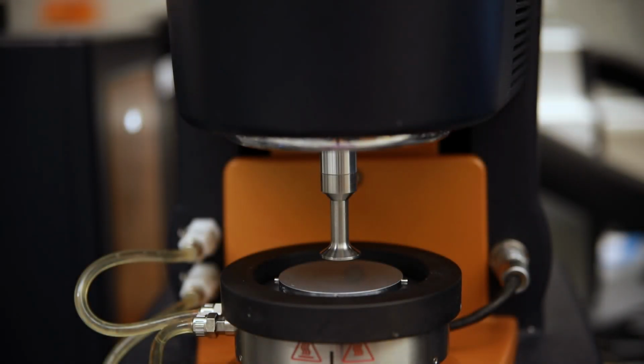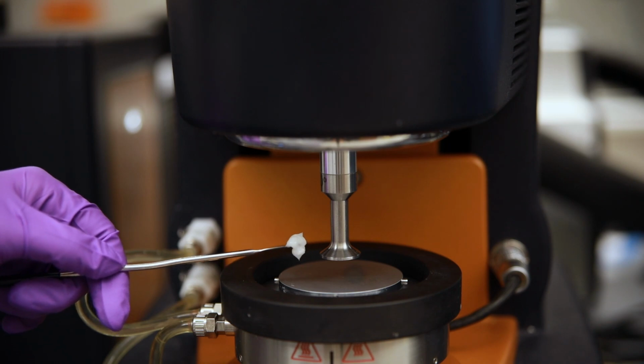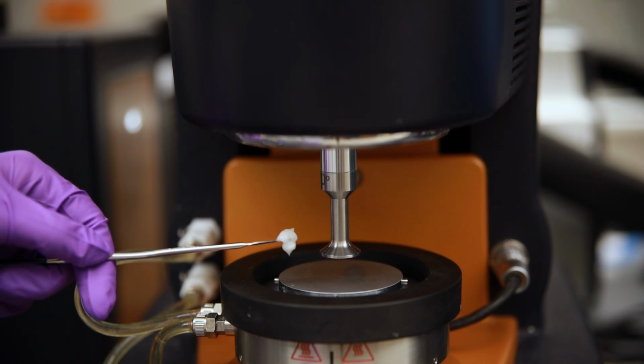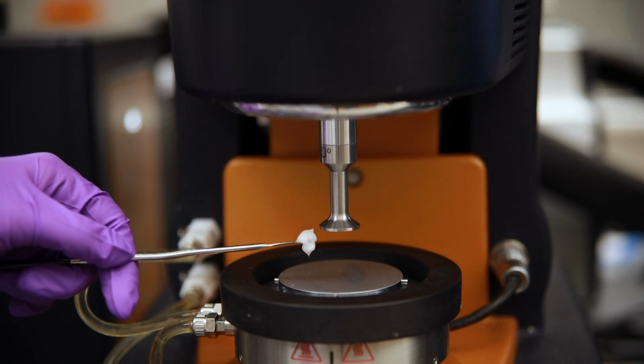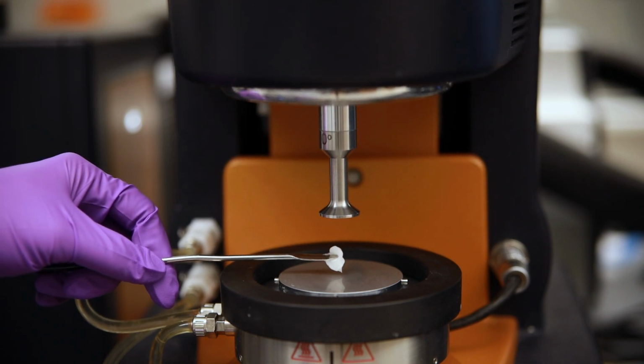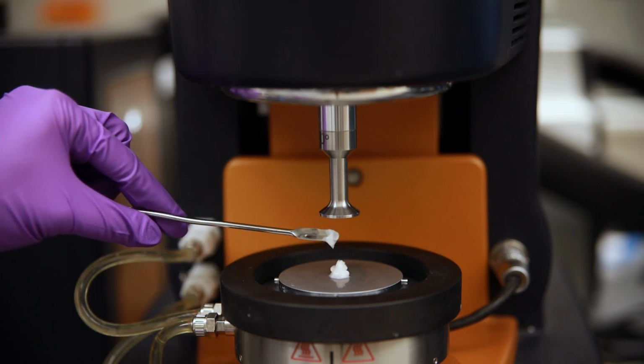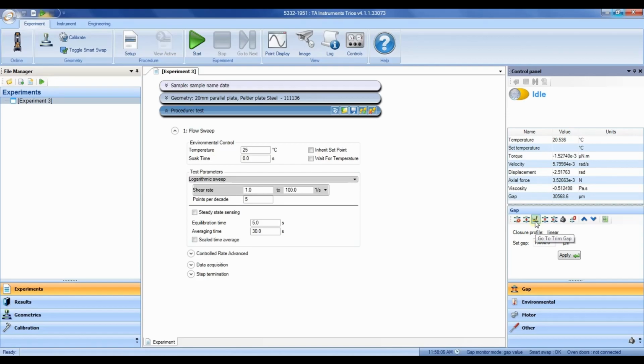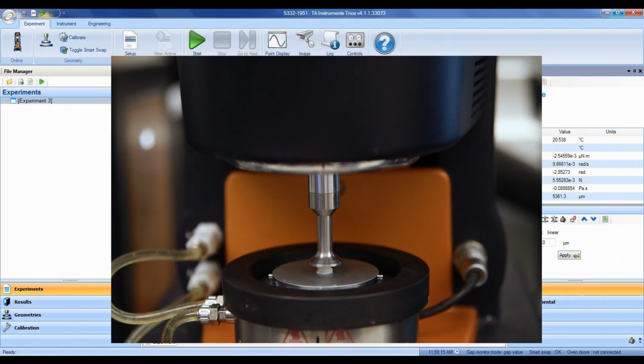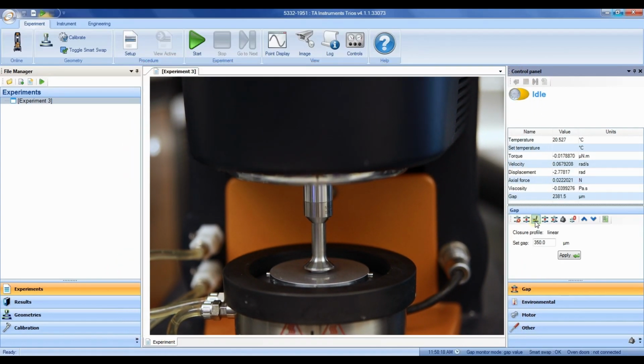Load your sample between both the plates. If the gap is too tight, you can move the plates apart by pressing the upward arrow here. Add your sample to the center of the plate. Click on Go to Trim Gap. At this point, you should see your sample squeezing out between both the plates.